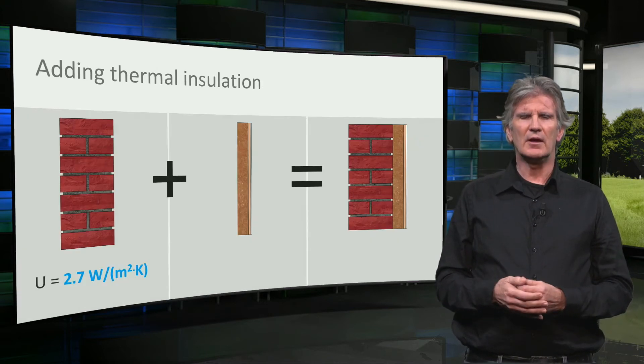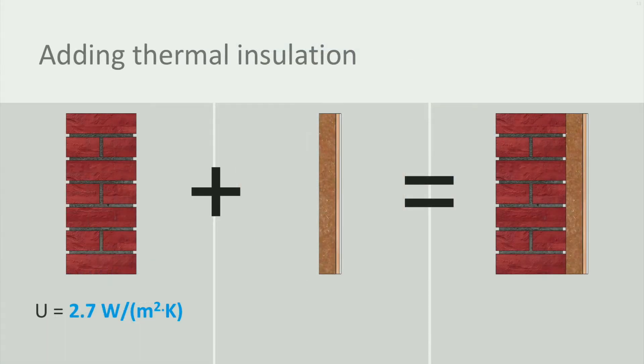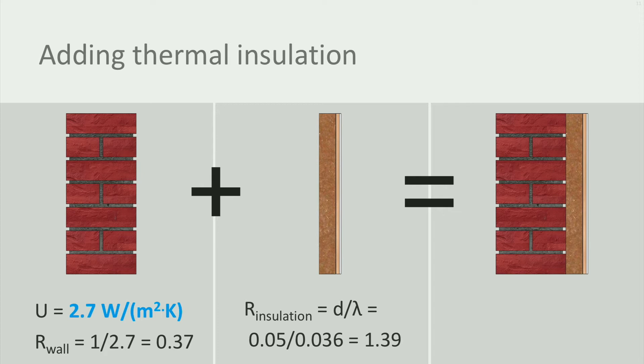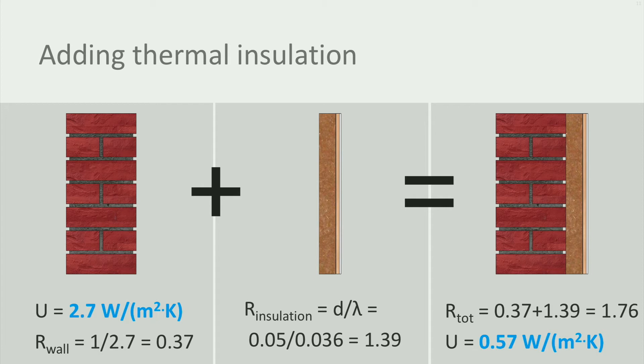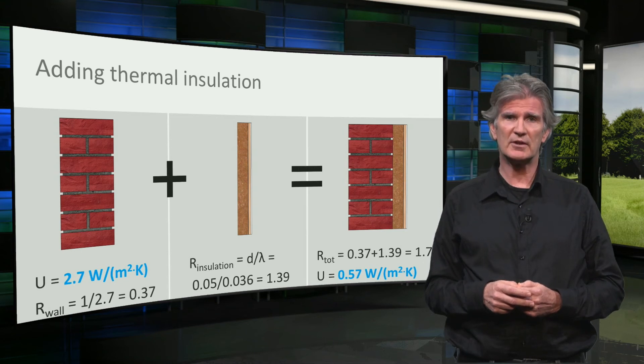Let us look at an uninsulated wall and see what happens if we add a layer of thermal insulation. The U-value of the uninsulated 20 cm thick masonry wall is 2.7, so the total thermal resistance is 1 divided by 2.7, which is 0.37. A 50 mm layer of mineral wool insulation has a thermal resistance of 1.39, so the total thermal resistance becomes 1.76. This results in a U-value for the insulated wall of 0.57.